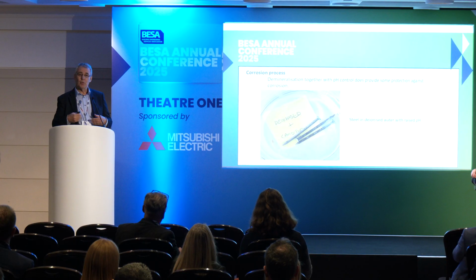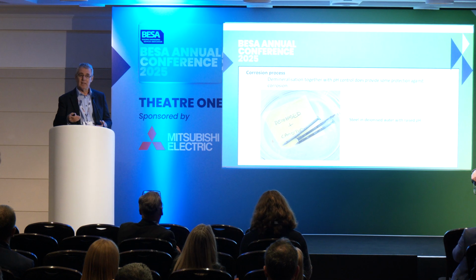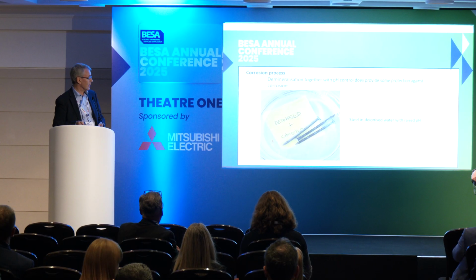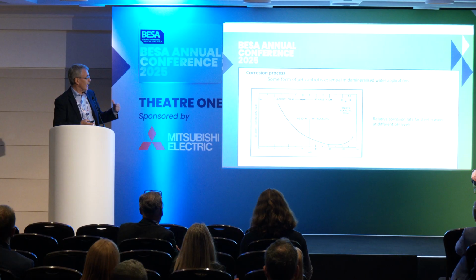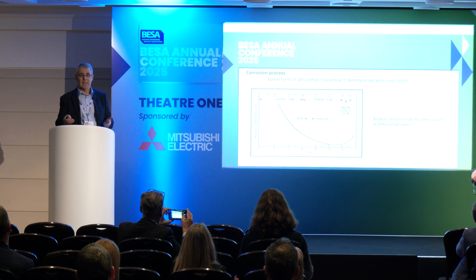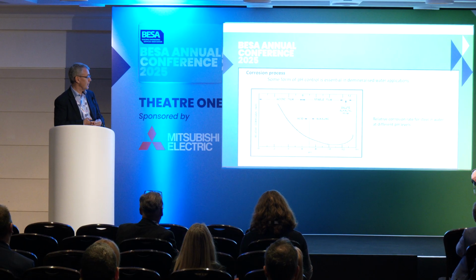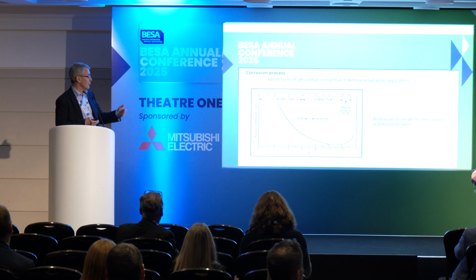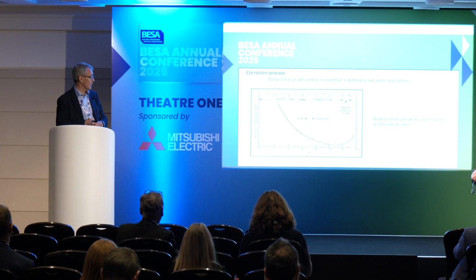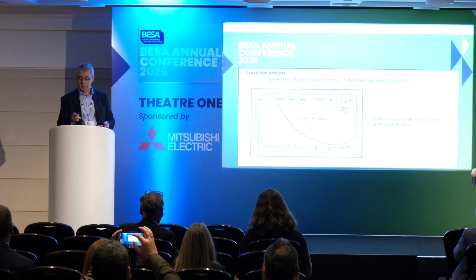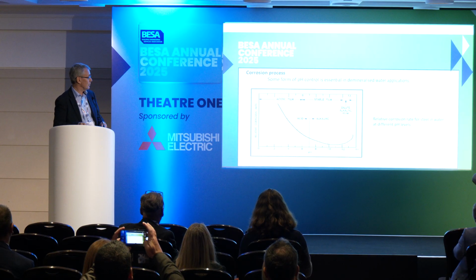But if you control pH, so if you keep the pH up high enough, then it becomes a very effective method of controlling corrosion. And that's following basic chemistry of systems. If you keep the pH level high enough, in the range between 8 and 10 or 11, then you minimise the corrosion from the water.